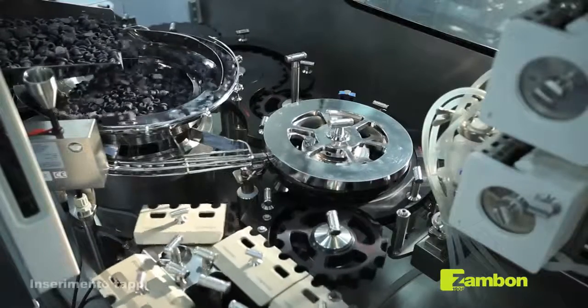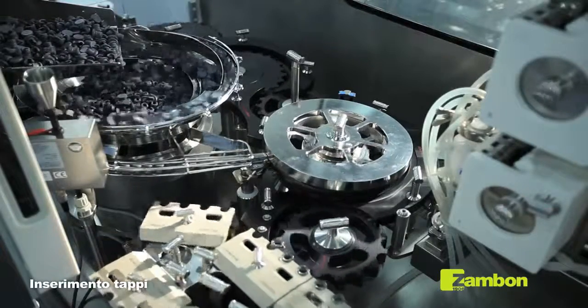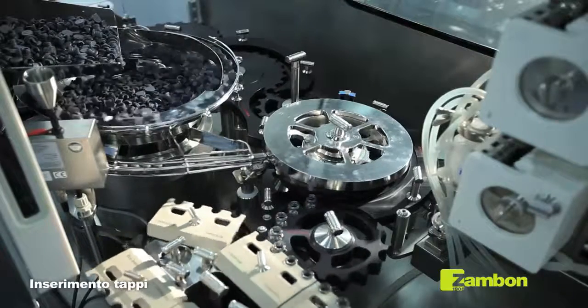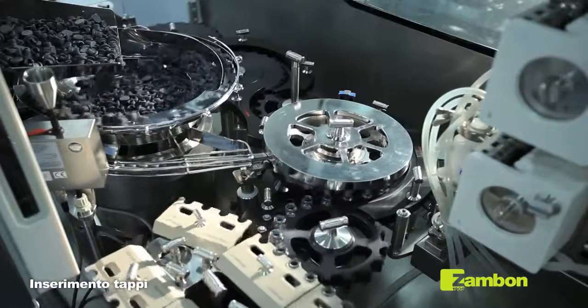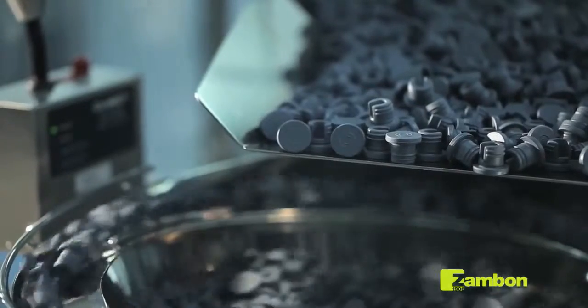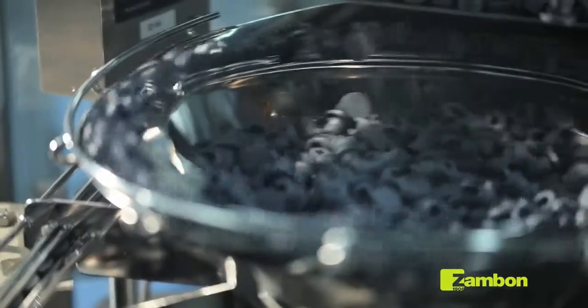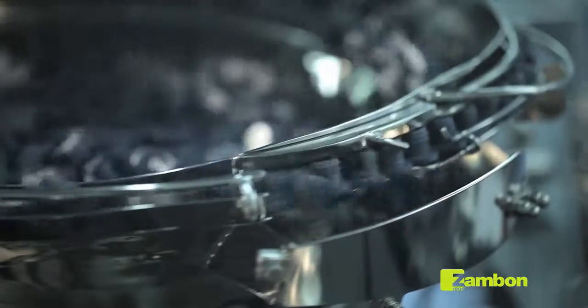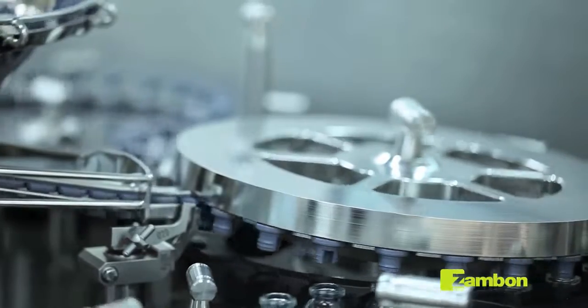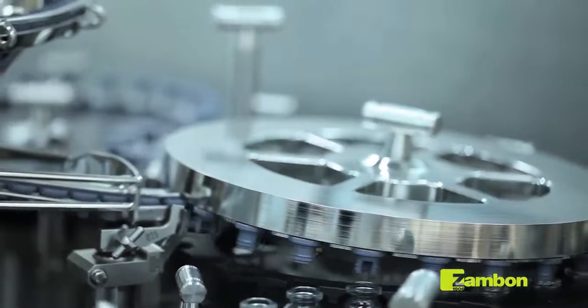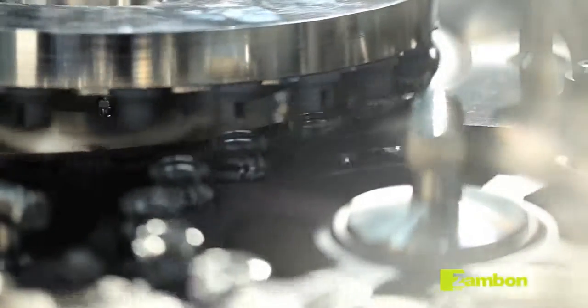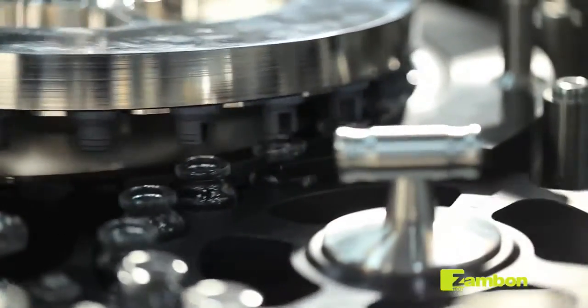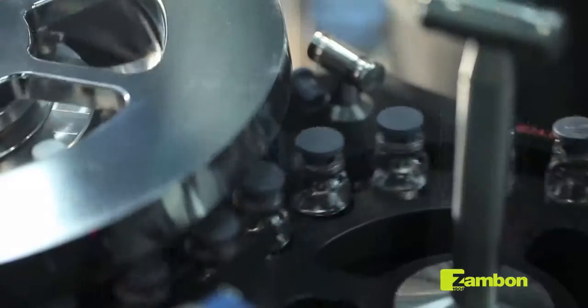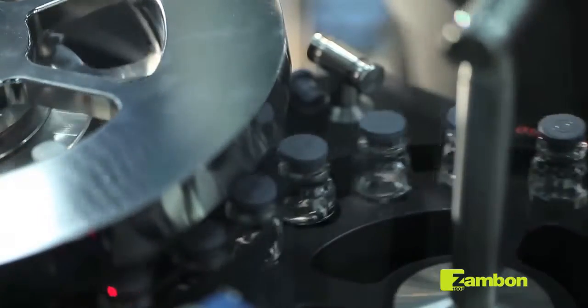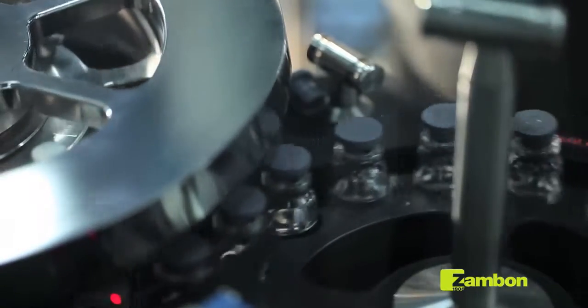The capping station is placed at the rear of the filling machine. The operator loads the sterilized caps onto the hopper of the bottle capper. The caps are fitted with a side opening to enable the evaporation of the water during the lyophilization. This is why the caps are positioned on the bottle without being completely inserted. The machine checks the correct insertion by means of an optical sensor.